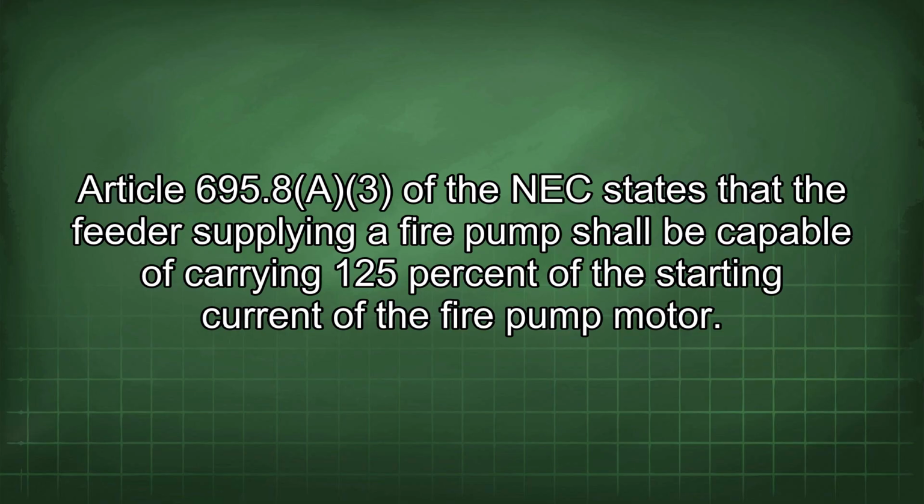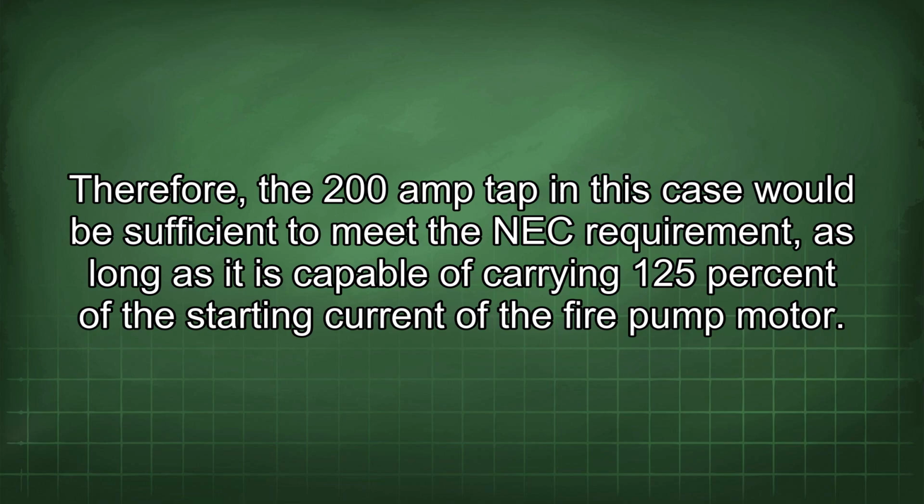Article 695.8 of the NEC states that the feeder supplying a fire pump shall be capable of carrying 125% of the starting current of the fire pump motor. Therefore, the 200 amp tap in this case would be sufficient to meet the NEC requirement, as long as it is capable of carrying 125% of the starting current of the fire pump motor.